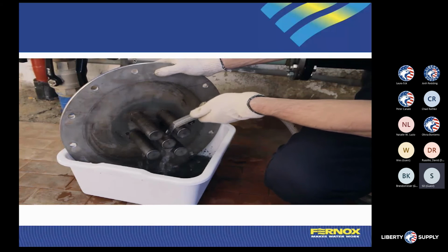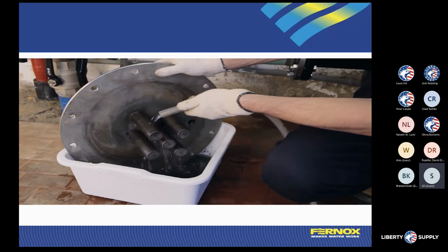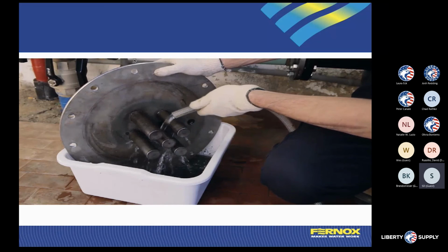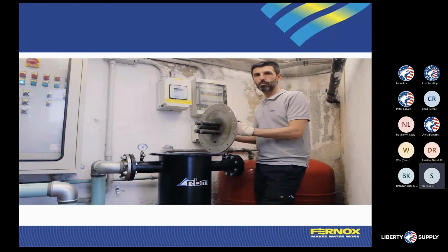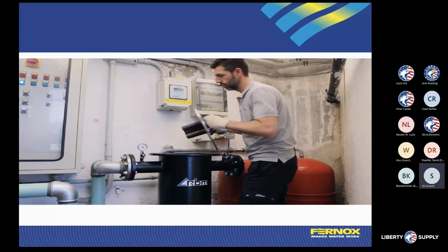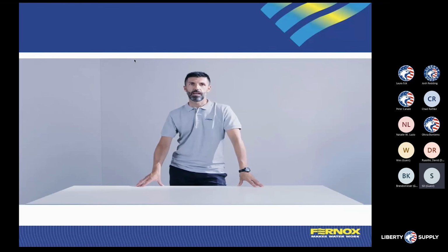So essentially, we're going to pull the screen out. We're going to flush the system down. We're going to clean out the contaminants out of that magnetic filter. This is our capture point. So again, if we're using that filter fluid, this is the place where we would be able to remove all that sediment, all of that debris, as well as be our refill point for any of our inhibitor as far as that's concerned.